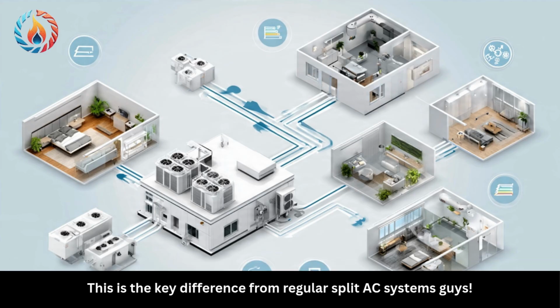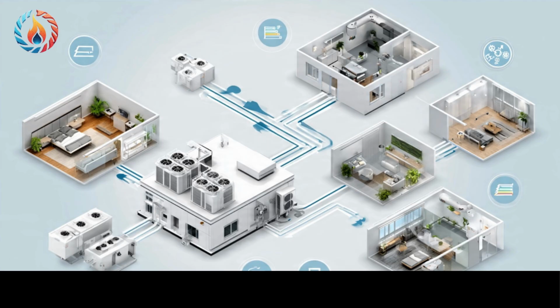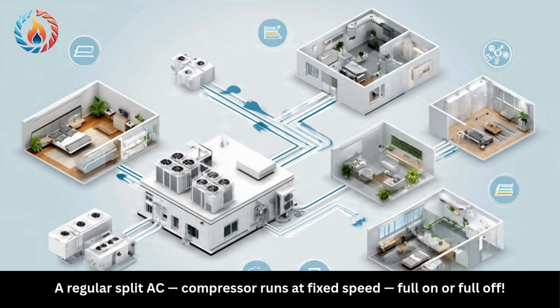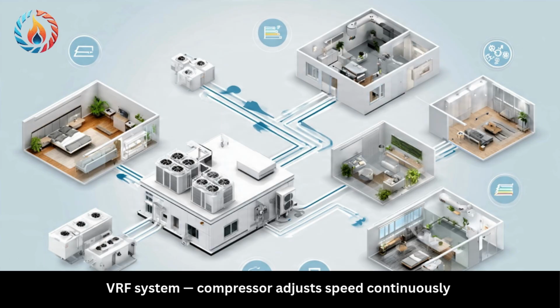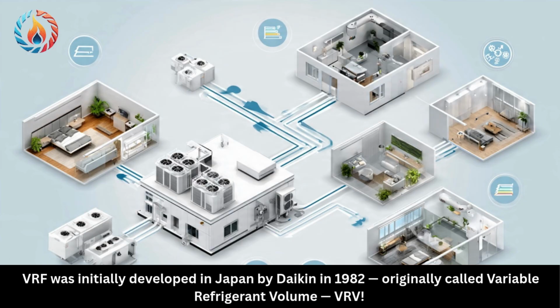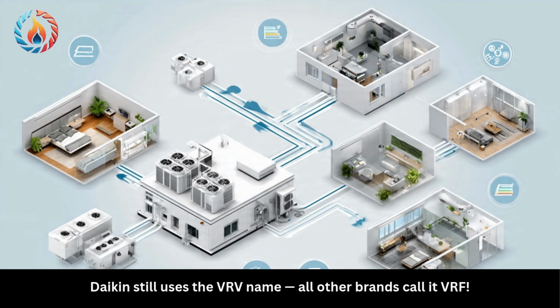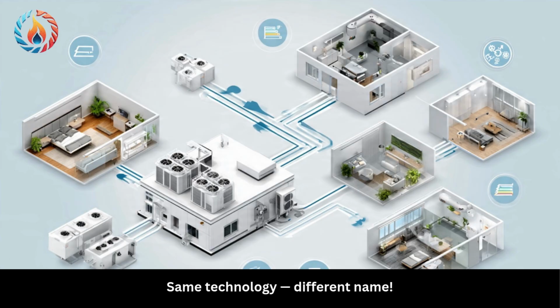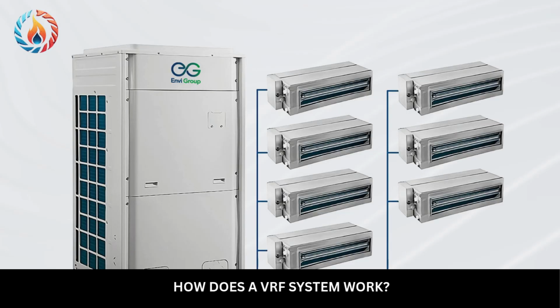This is the key difference from regular split AC systems, guys. A regular split AC compressor runs at fixed speed, full on or full off. VRF system, compressor adjusts speed continuously, giving each zone exactly what it needs. VRF was initially developed in Japan by Daikin in 1982, originally called Variable Refrigerant Volume, VRV. Daikin still uses the VRV name. All other brands call it VRF. Same technology, different name.